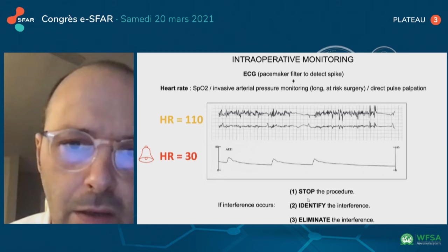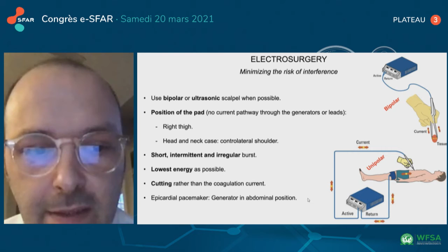How to minimize the risk of interference during electrosurgery? If you can, of course, use bipolar or ultrasonic, with a very low risk of interference. Optimize the position of the pad for unipolar surgery on the right side if you can, and for head and neck surgery on the contralateral shoulder. Use short, intermittent, irregular bursts at the lowest energy possible, and prefer the cutting energy compared to the coagulation current.